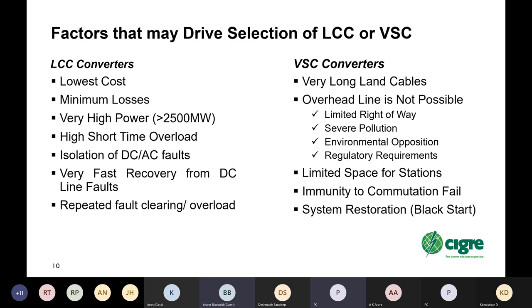Where the overhead line is not possible, possibly due to limited right-of-way or severe pollution or environmental opposition, regulatory requirements, and you then opt for a cable, then that may be the only way that it can be done. And of course, with VSC converters, with the cables being cheaper, it would be obviously an advantage to go with VSC in that scenario. If you have limited space for converter stations, you would consider VSC, because VSC converters don't include very large filters, so the space requirement for the stations is quite a lot smaller than for LCC converters.